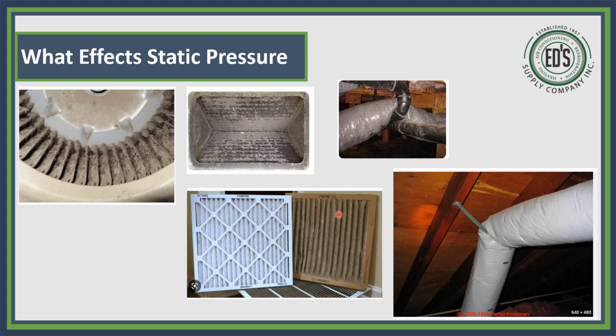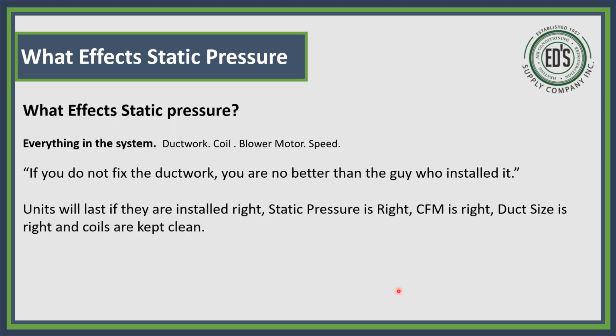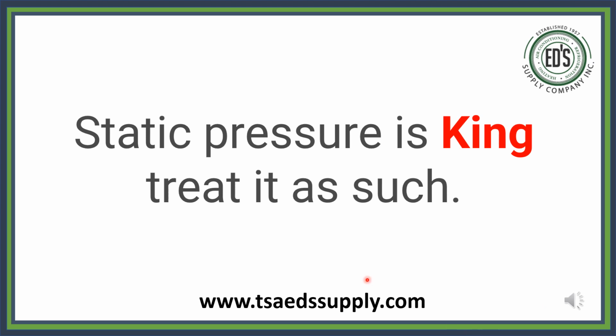That's resistance caused there. A dirty filter causes resistance, and in the attic, when this gets hot, that inner liner breaks down and collapses right here, and you can see all the weight from this flex just dangling here. That's going to cause resistance as well. What affects static pressure? Everything in the system: ductwork, coil, blower motor, speed. If you don't fix the ductwork, you're no better than the guy who installed it. Units will last if they're installed right: static pressure is right, CFM is right, duct size is right, and the coils are kept clean. Static pressure is king, so treat it as such.